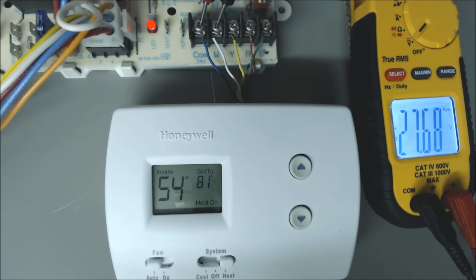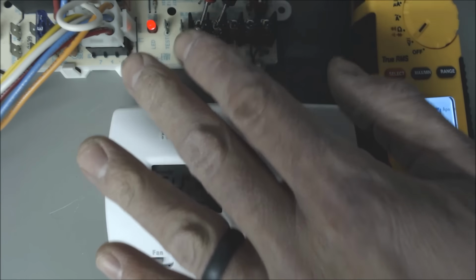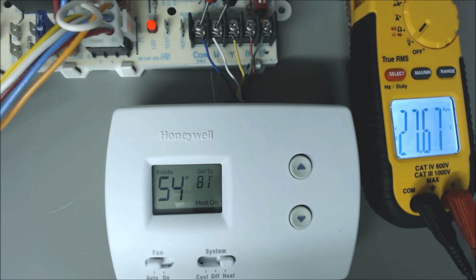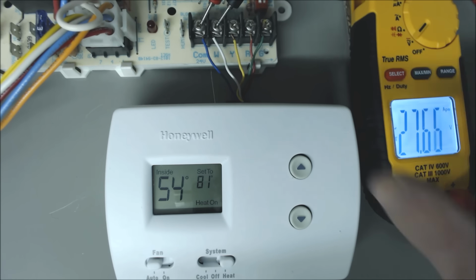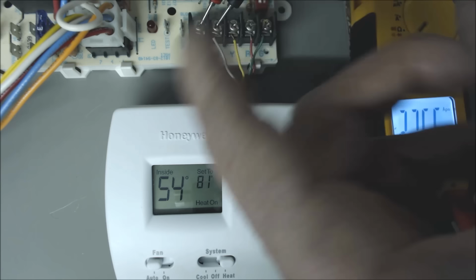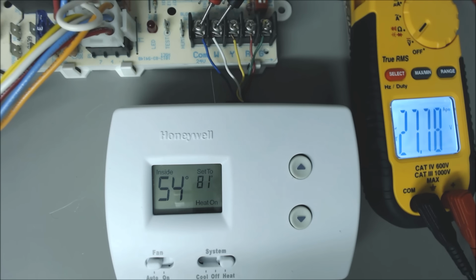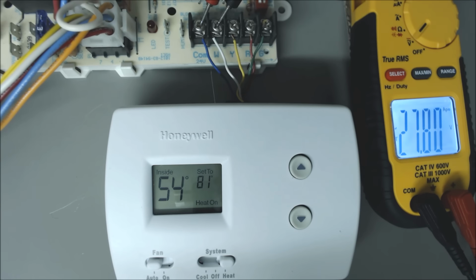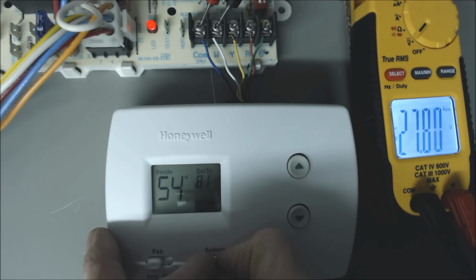So you see we're reading 27.69 volts. That's telling us that the control board is receiving the signal for heat, and right now you can see that our LED status code light is actually flashing. That's one of the things that you want to look for, so that if the heat is not turning on, you have an idea of what's happening or what the problem is. So right here we have 27 volts indicating that heat is calling.